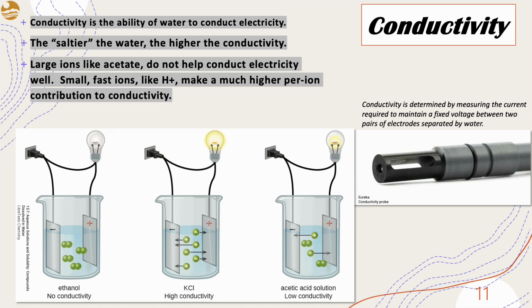But the conductivity measurement cannot tell you the concentration of ions in water, because different ions have different contributions to conductivity. A large ion like acetate does not help conduct electricity well. A smaller, faster ion like H+ makes a much higher per-ion contribution to conductivity. So natural waters usually have a mixture of ions, and the conductivity reading is only a relative measurement of ion concentration.